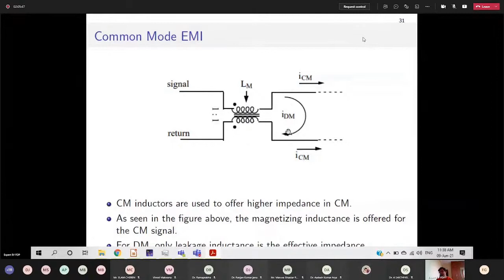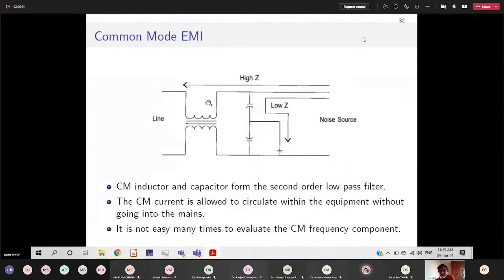So these are the simplest common mode inductors available, and you will have to design them again to get sufficient inductance. When you're designing this, you need to take into account that the leakage is very low. Otherwise, you would simply be adding additional inductance for the differential mode signal. And this is just to highlight the path. So this is the common mode inductor, and if this is the noise capacitor, which connects between both the line and return to the common ground, the current goes here, and this would offer higher impedance so that it doesn't enter inside.